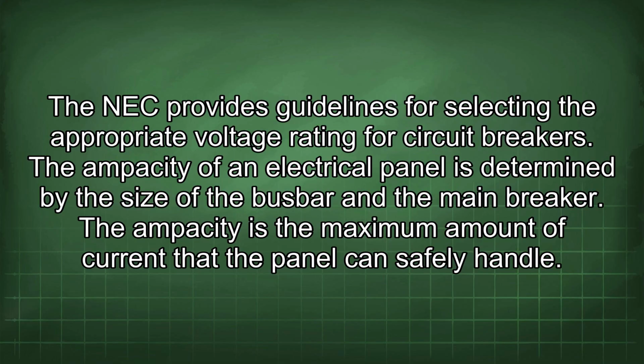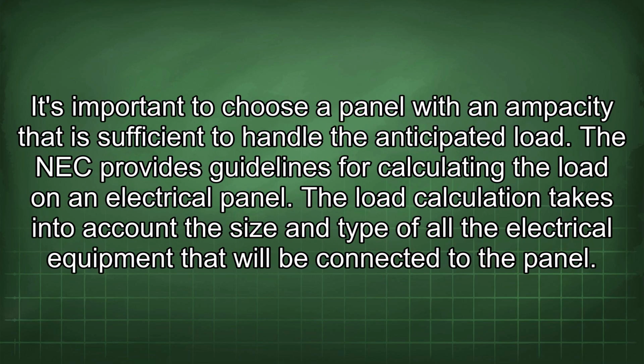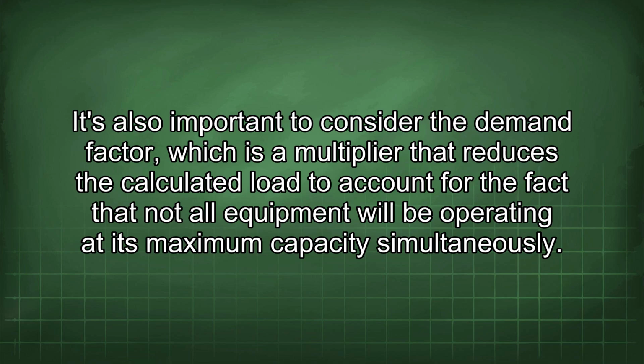The ampacity of an electrical panel is determined by the size of the busbar and the main breaker. The ampacity is the maximum amount of current that the panel can safely handle. It's important to choose a panel with an ampacity that is sufficient to handle the anticipated load. The NEC provides guidelines for calculating the load on an electrical panel. The load calculation takes into account the size and type of all the electrical equipment that will be connected to the panel. It's also important to consider the demand factor, which is a multiplier that reduces the calculated load to account for the fact that not all equipment will be operating at its maximum capacity simultaneously.